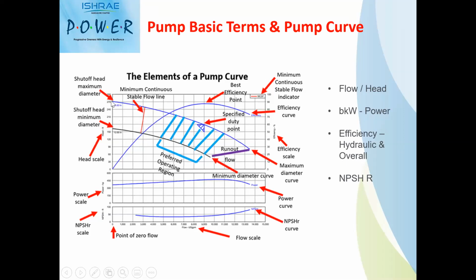The curve which touches on the y-axis is called shut-off head. So when you close the valve on the discharge side, the pump will keep on generating head, but it will not give any flow because you are obstructing the discharge side of the pump. At that point, the maximum pressure or maximum head attained is called closed valve pressure or shut-off head. This value is the maximum diameter shut-off head. This is the minimum diameter of the pump, and this is the minimum shut-off head.